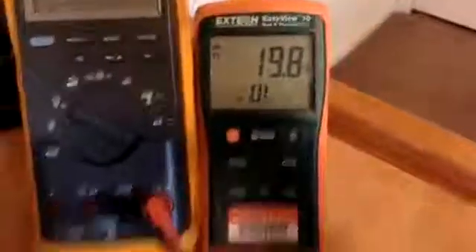So in order to calibrate the thermistor, we need to take temperatures at multiple different points. So what you need for this is a thermometer of some sort, in this case we're using a thermocouple, some water at different temperatures, and a voltmeter as well as the instrument. So what you want to do is you want to take the temperature of the water which we have here at the thermocouple, which happens to be around 20 degrees Celsius.